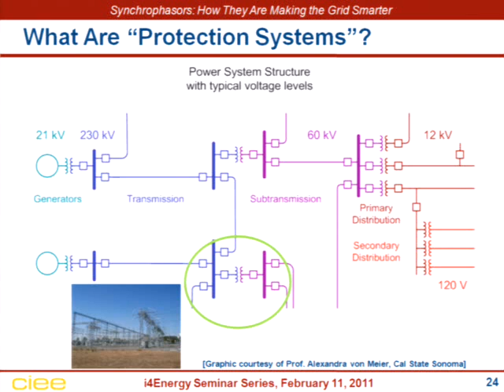There's a big circuit breaker - these are three single-phase circuit breakers. What I showed you before was a single-line diagram, which only shows one phase of a three-phase system, for simplicity, since all three phases are supposed to be balanced and the same. But in real life, this is an oil tank circuit breaker - you can see the little spigot at the bottom where you can drain it. Modern circuit breakers use gas, SF6, as the insulating medium, so they're called gas insulated breakers - that's normally what you buy these days. But these are the devices that actually interrupt the power.